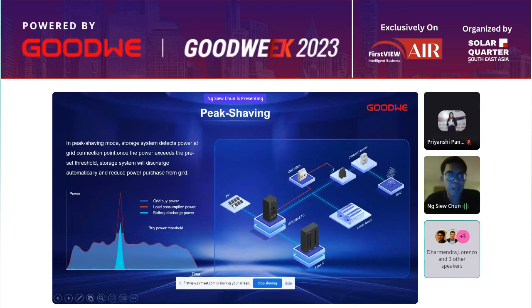The next part would be the peak load shaving module. This algorithm is also integrated into our storage system. Basically, clients could set the maximum demand threshold via the app. Once the incoming power purchased from the grid hits or exceeds this pre-configured threshold, our battery system will automatically discharge power to compensate or reduce the maximum demand purchased from the grid. By that, we are able to control the maximum demand surcharge charged by the grid.